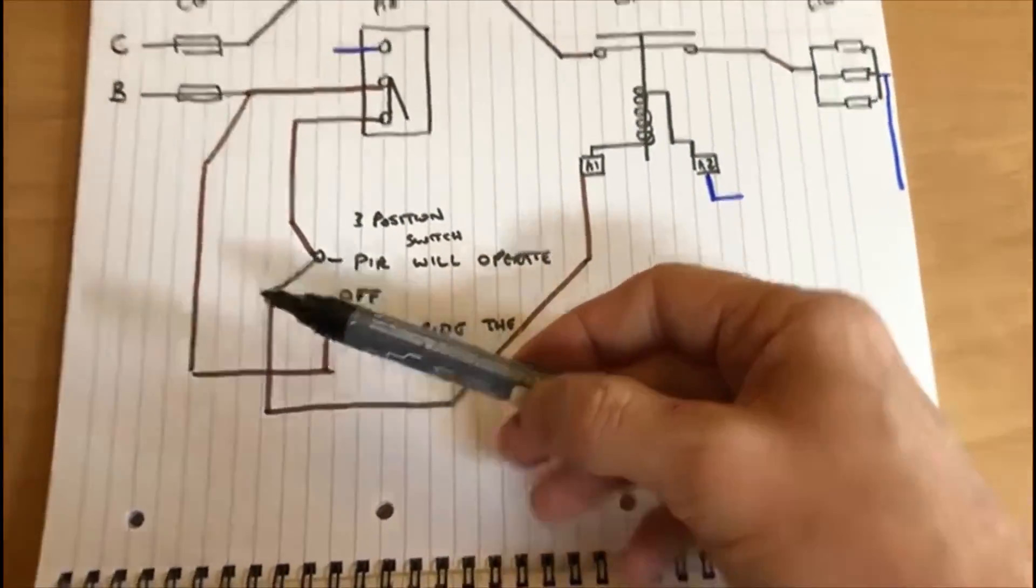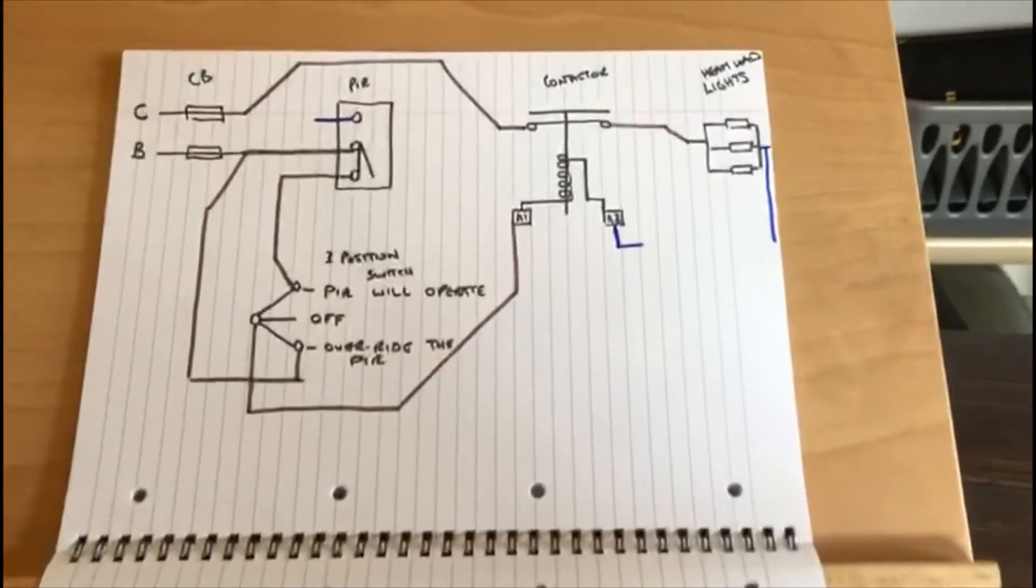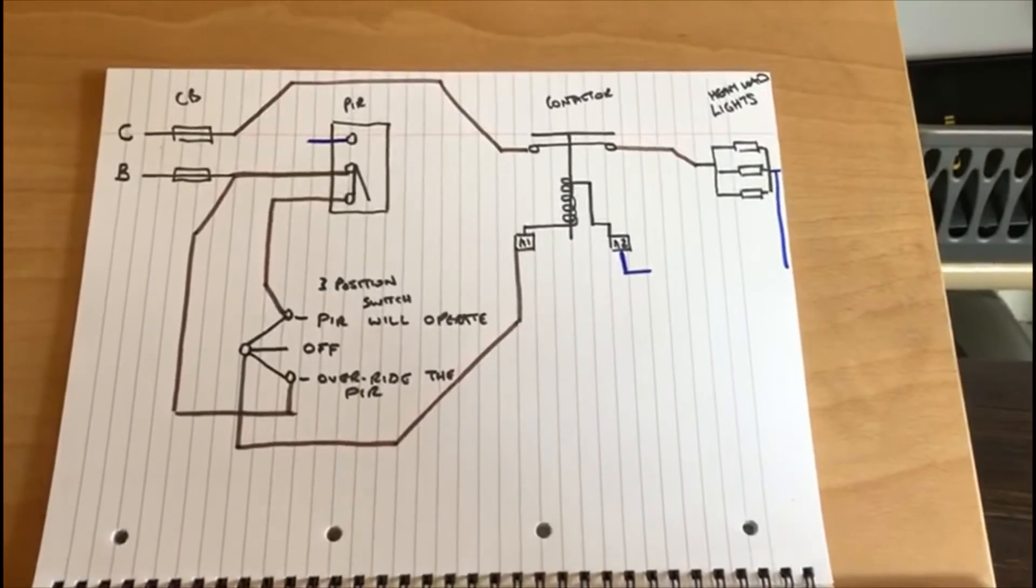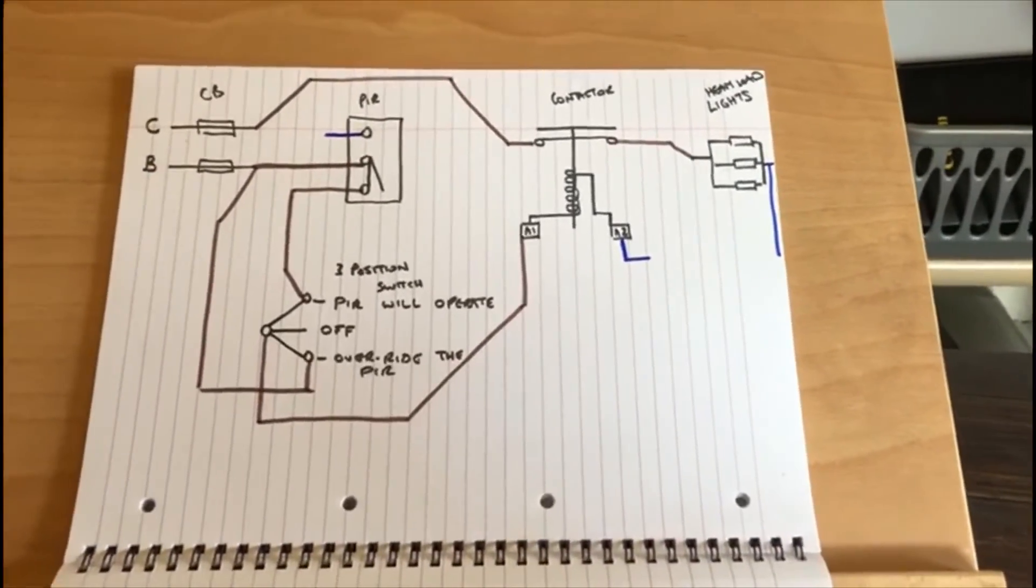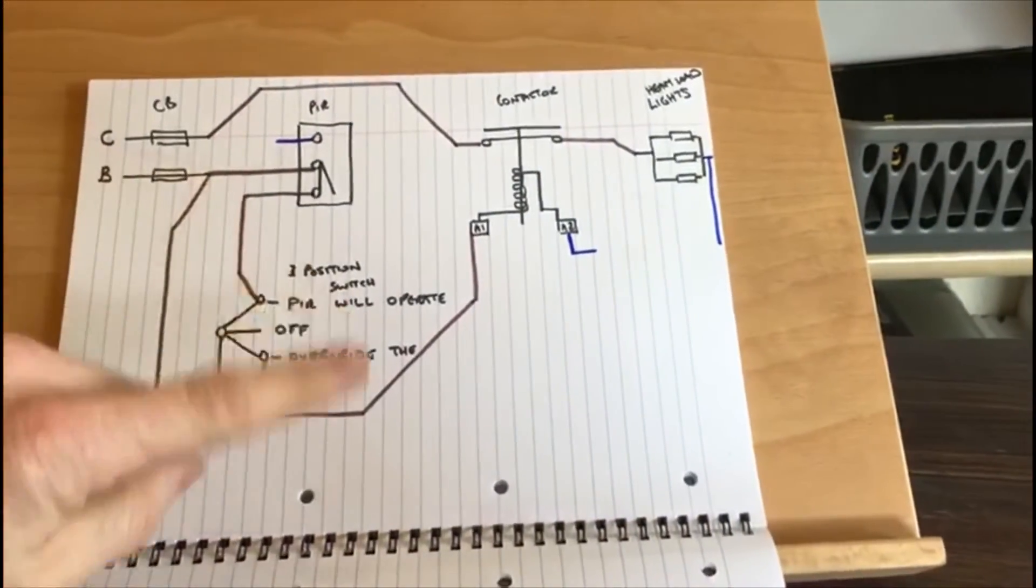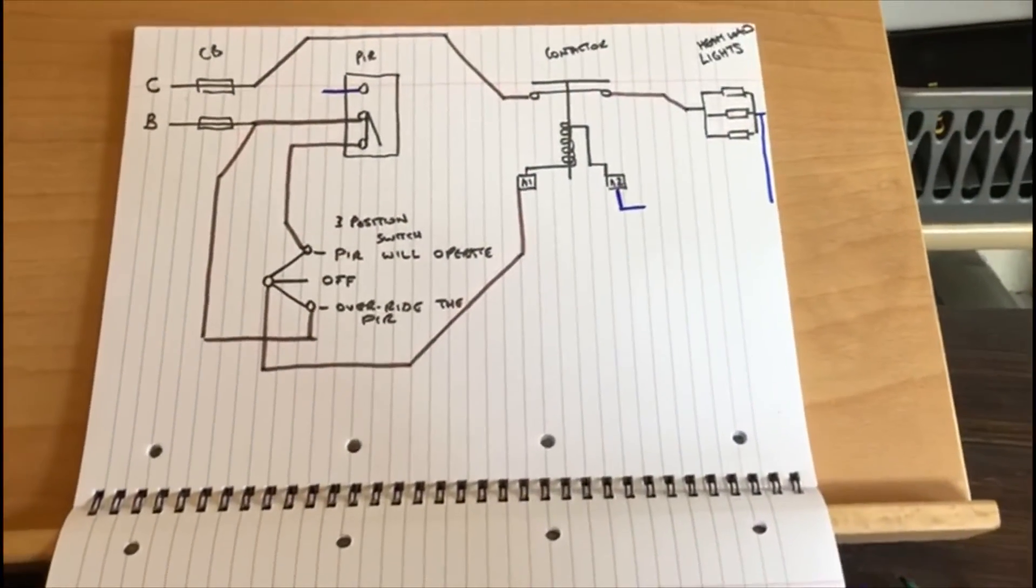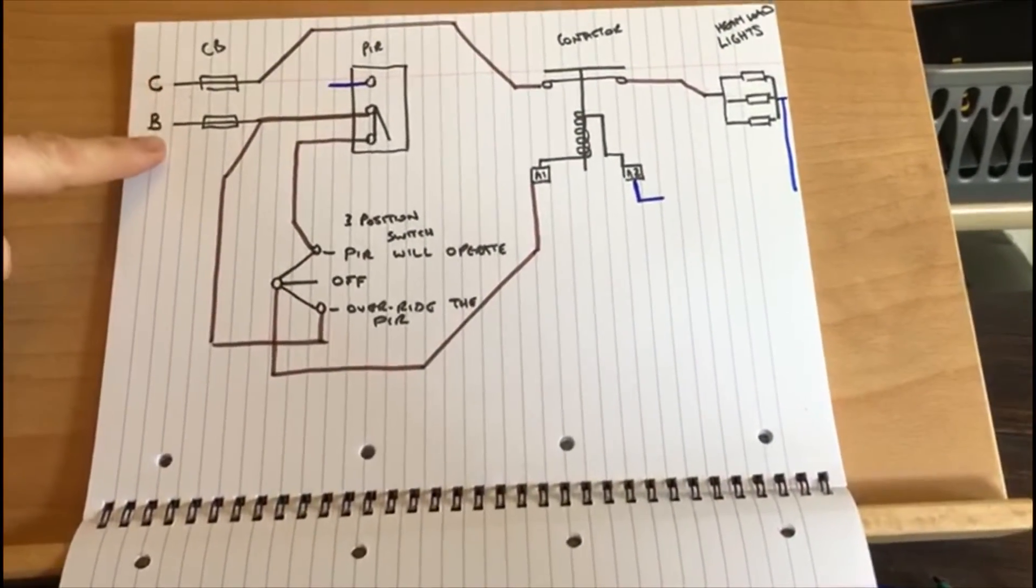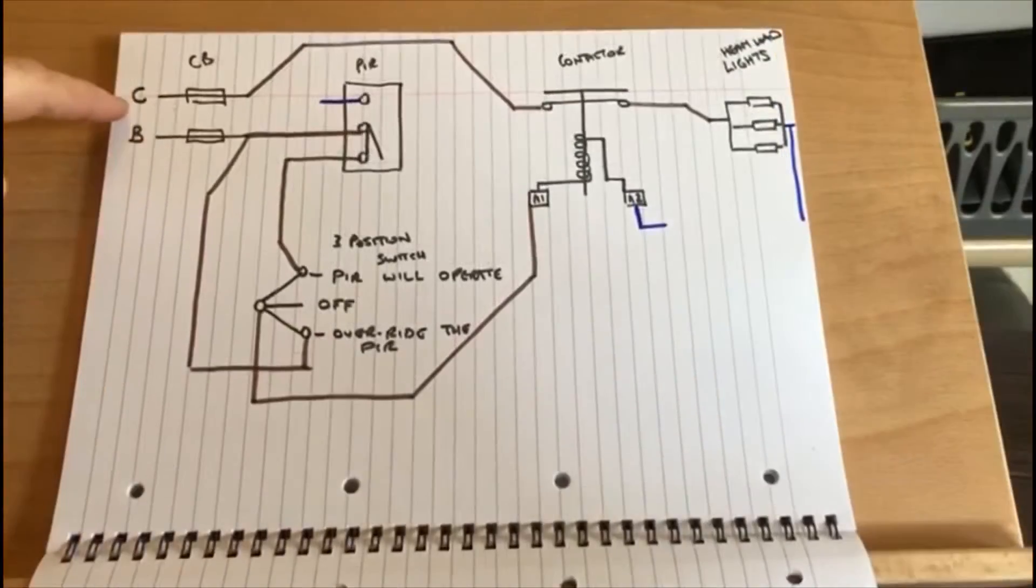So again that's the use of a three position switch which is quite common in industry, at least using the PIR, the contactor and a three position switch. In this case we've got the two types of circuit breakers, a C type and a B type. They need to be labeled in such a way that they know they are both for the same lighting circuit.